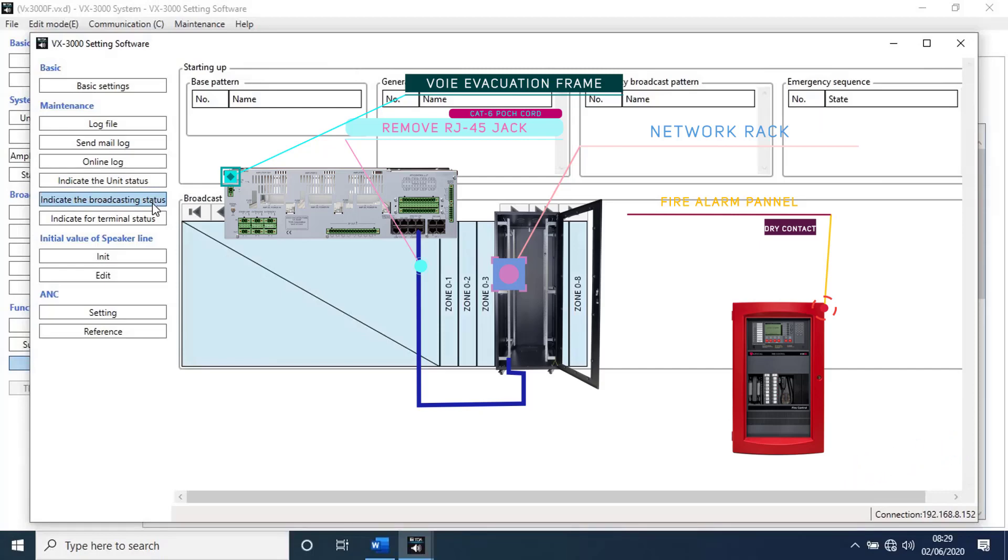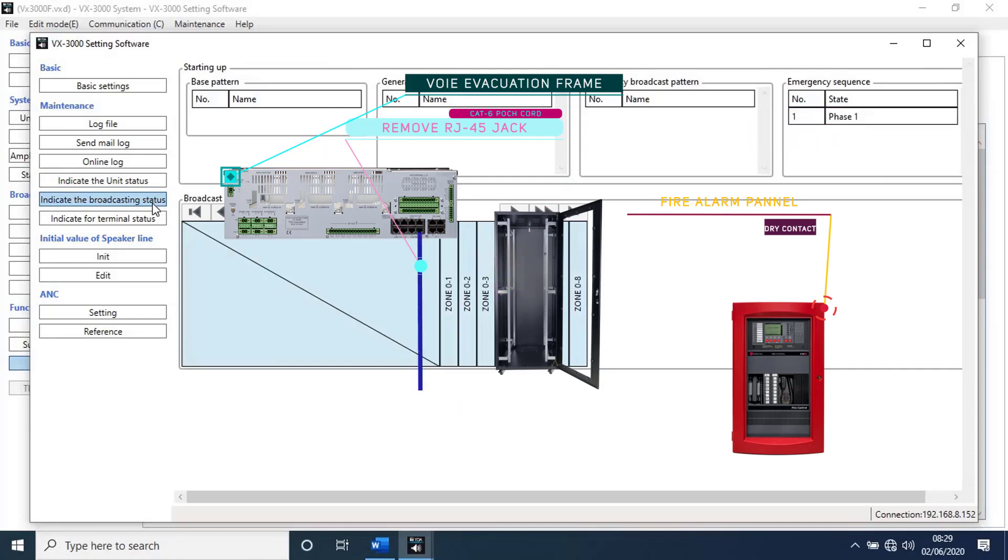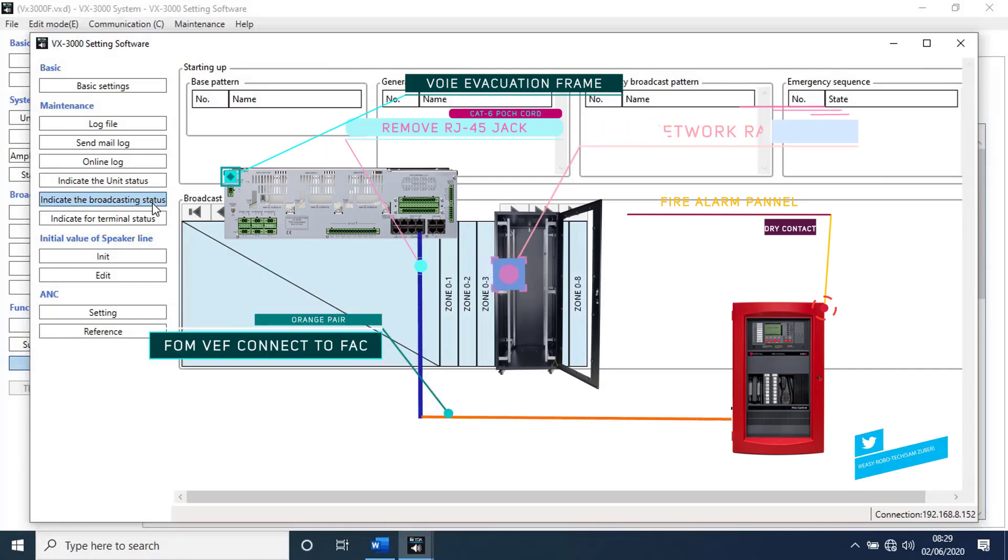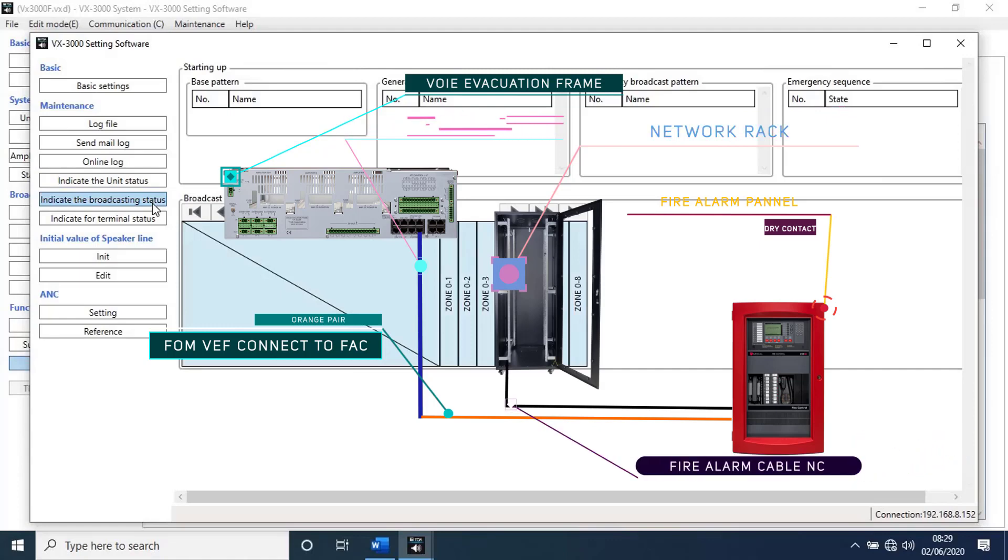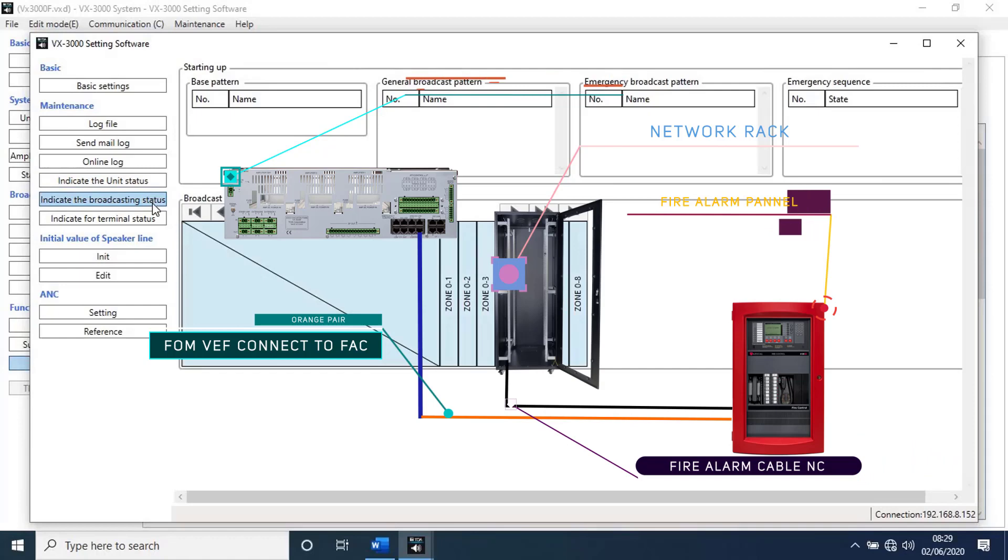To interface with fire alarm, we will receive a cable from fire alarm panel. Take normal open signal from panel. Then connect sliced orange pair to one cable and other cable connect to rack earthing. Once fire alarm activate, NO become close, then emergency sequence start broadcasting.